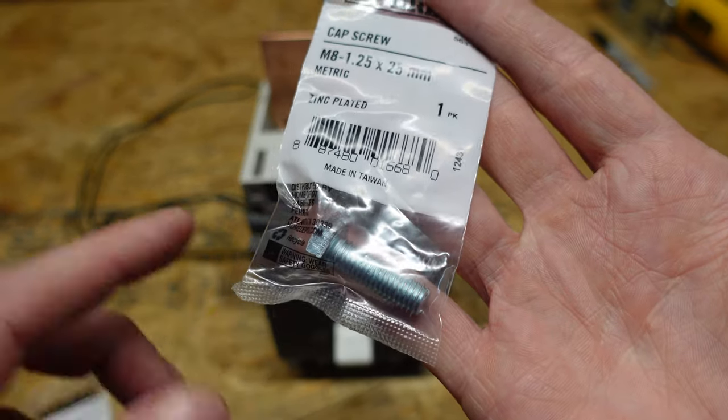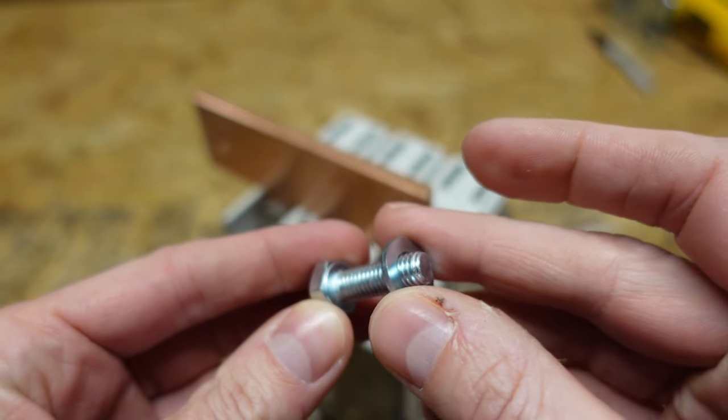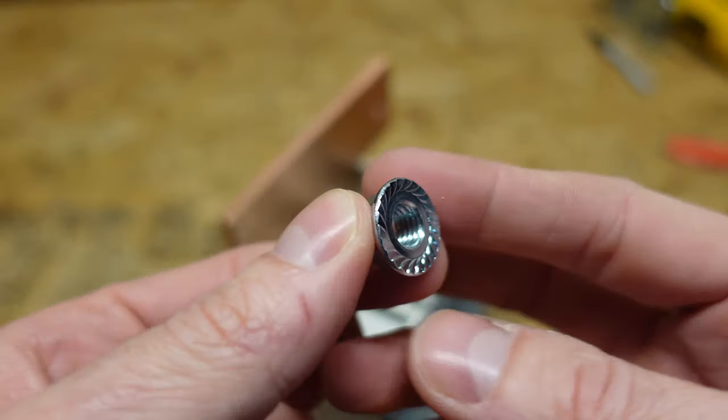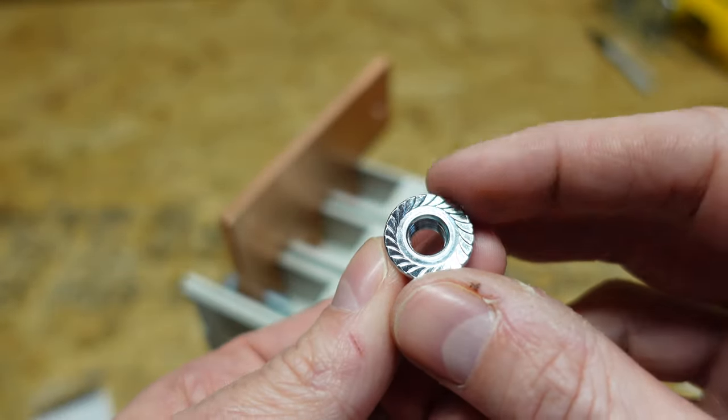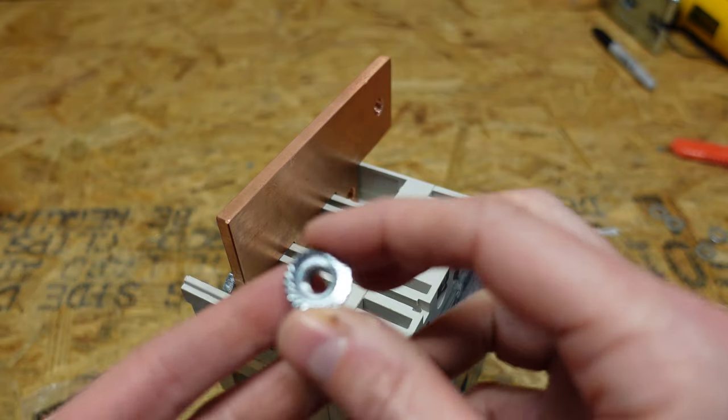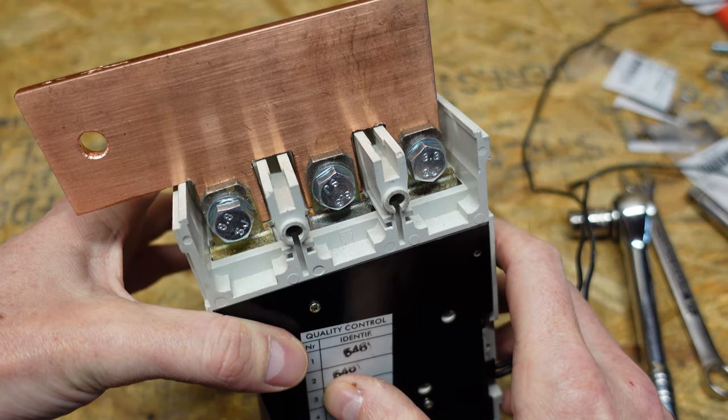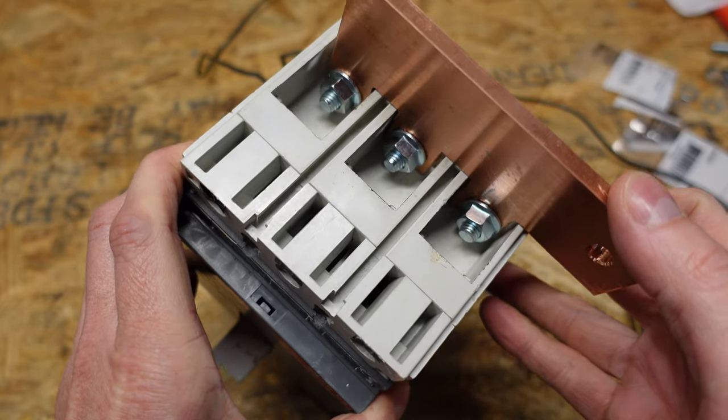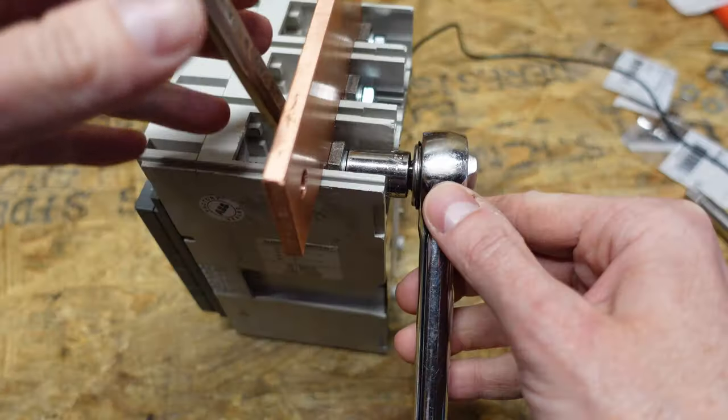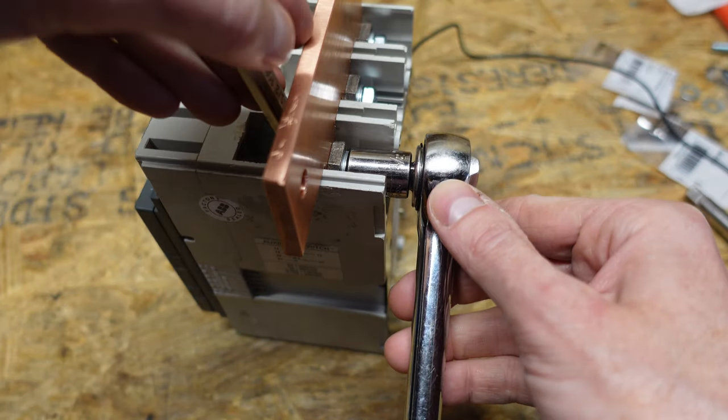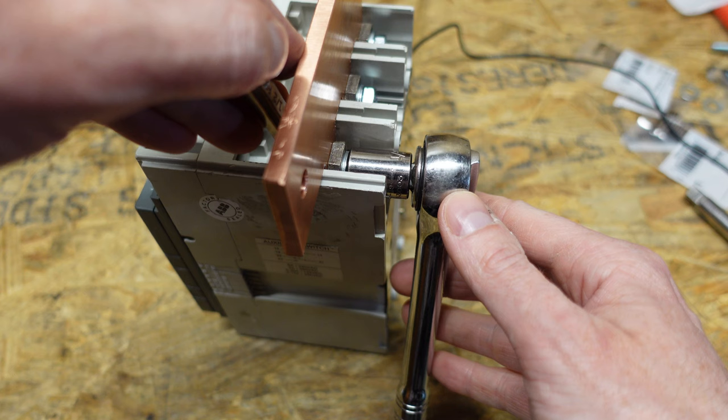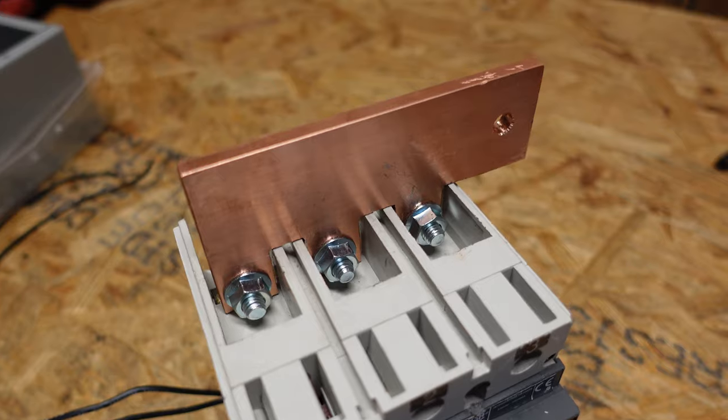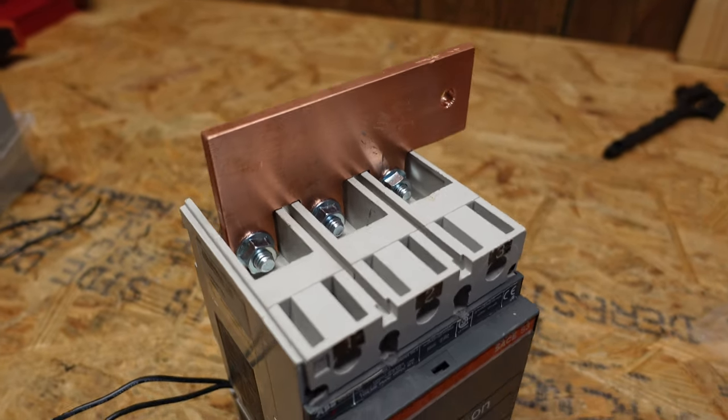I picked up some 16 millimeter and I picked up some 25 millimeter. We're going to use the longer bolt. So we got our longer bolt. We have a flat washer going to feed that up the bottom and then for the other side I have a serrated flange nut. So the serrated teeth will bite into this copper plate and help prevent it from ever backing back out. So here you can see the new bolts and washers on the back side and then on the front side we have the bolts and the serrated flange nuts. So for tightening I place the wrench on the flange nut and I have a ratchet on the back. That way the nut is not rotating as the bolt tightens. And here's how that looks from the front just once more because this is actually looking very very nice.